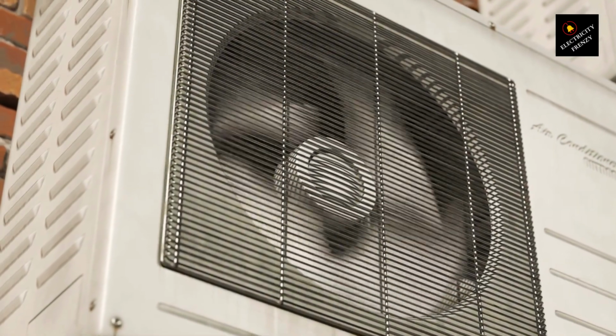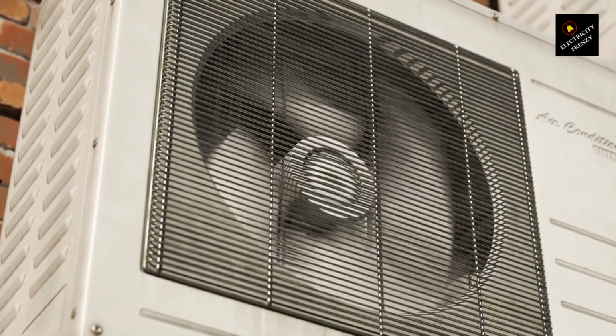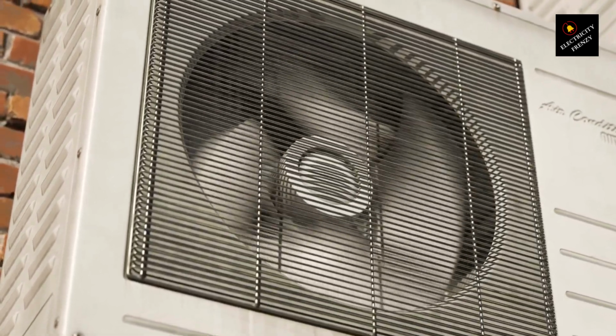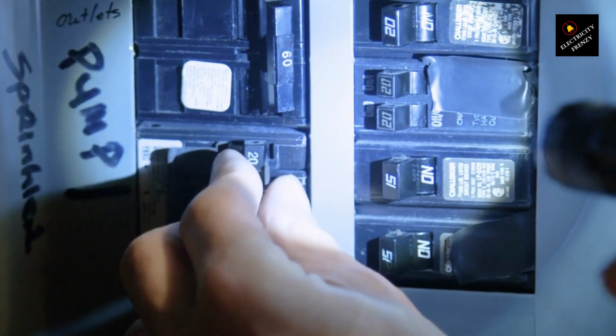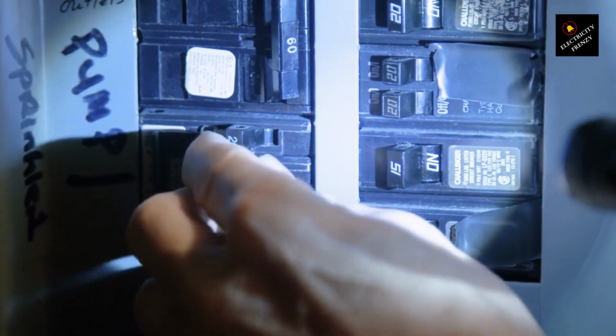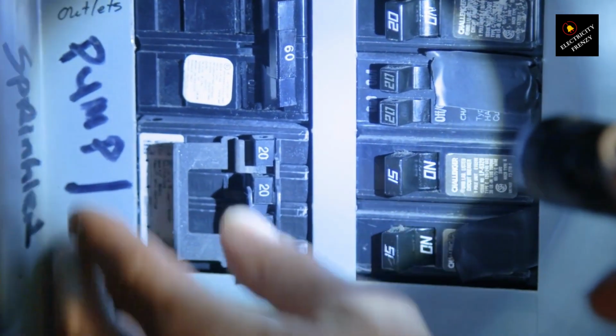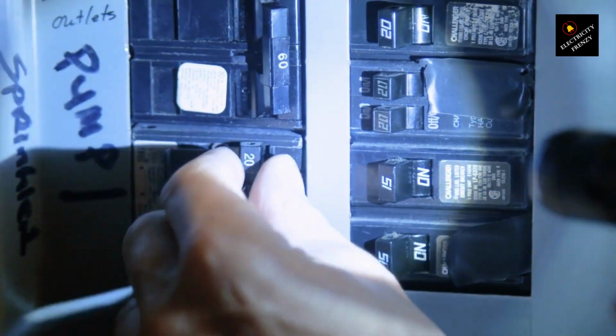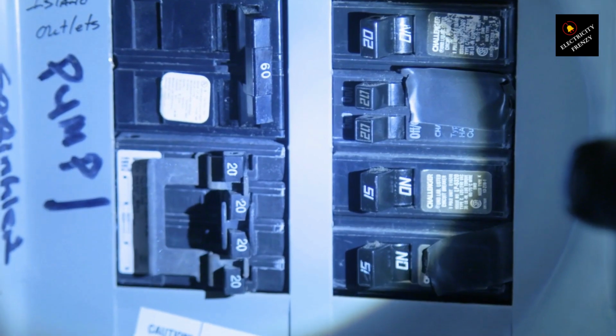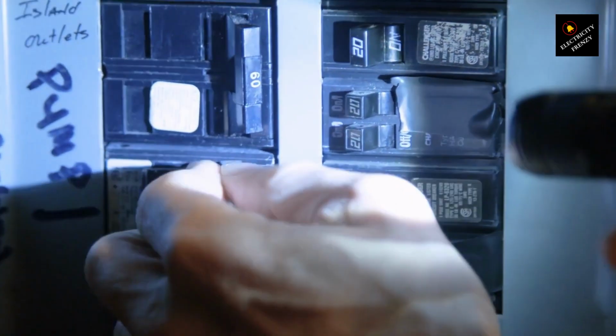Lastly, an overloaded circuit shared with other power-hungry appliances can push the limits of the electrical capacity, leading to breaker trips when your air conditioner kicks in. To diagnose an overloaded circuit, evaluate the electrical loads on the circuit by identifying the appliances sharing it. Add up their power consumption, in watts, and compare it to the circuit's maximum capacity, usually indicated on the circuit breaker. If the total load exceeds the circuit's capacity, it indicates an overload.